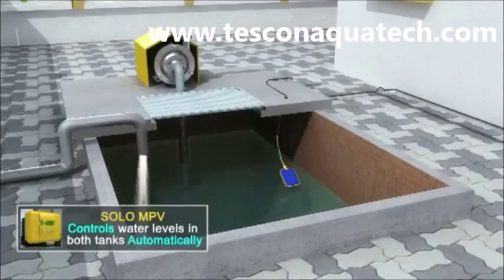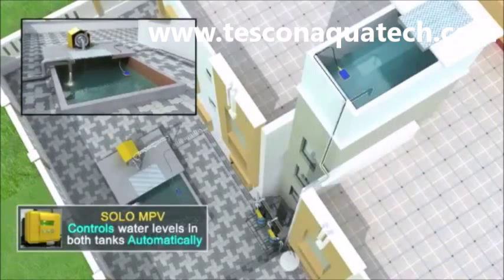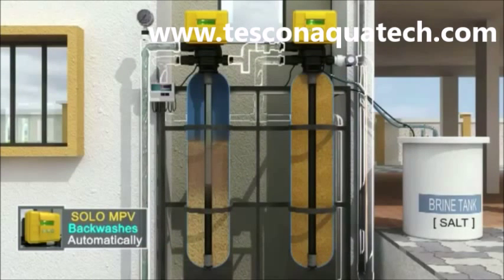Solo MPV performs the additional function of starting and stopping the raw water pump automatically based on tank levels. It switches off the raw water pump if the raw water tank level is low. When the treated water tank level is also low, it switches on the pump and switches it off when it is full.